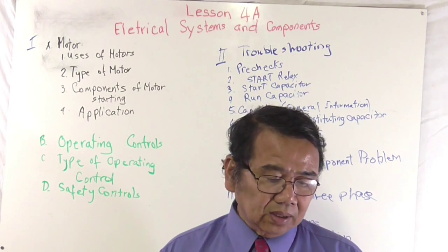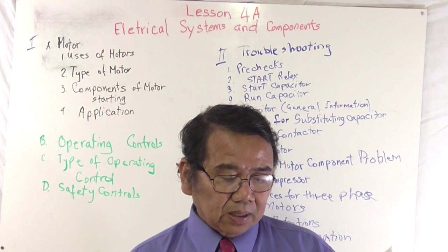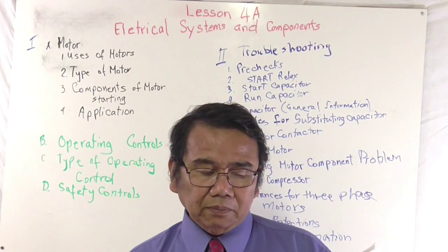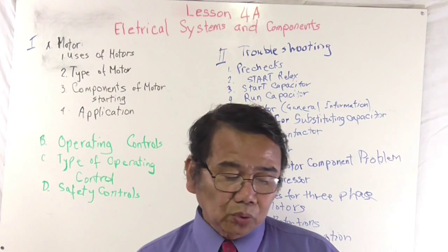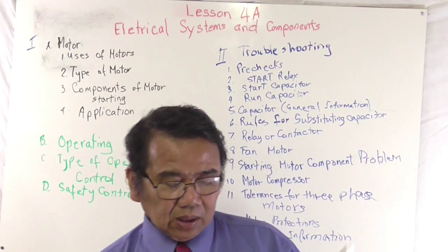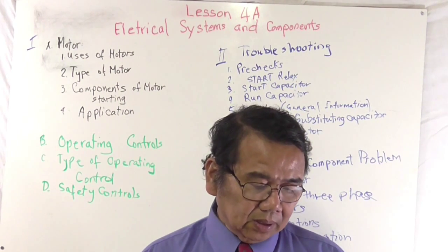And then you've got the start capacitor: the capacitance value can be equal to but not greater than 20% more than the one being replaced.